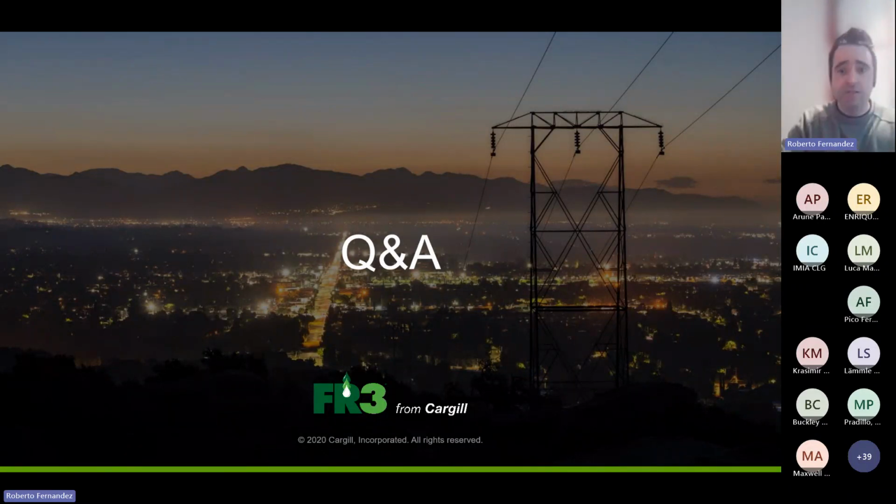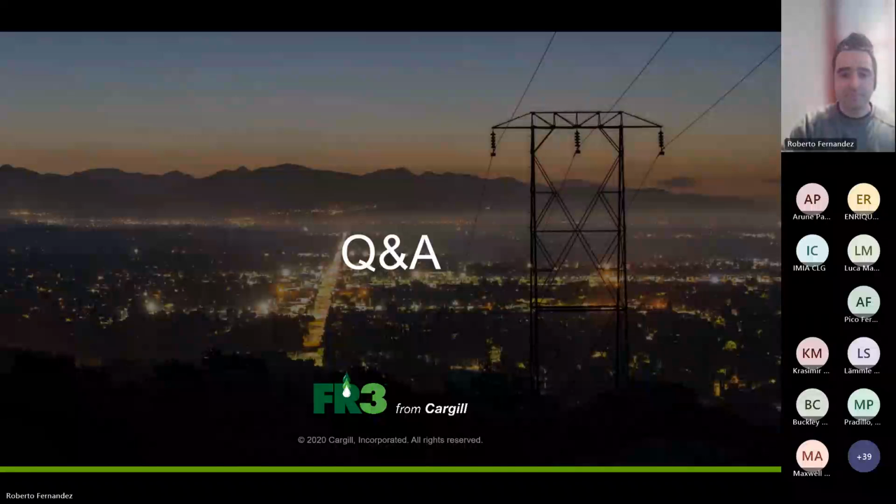And yes, on IEEE, there are two different standards for DGA, one for mineral, another for esters. In IEC, there is one for mineral, and we are working on the one for esters. We had a meeting a couple of weeks ago, just trying to finalize the writing of the standard itself, and it will probably be published next year. Okay. Thanks for the clarification.